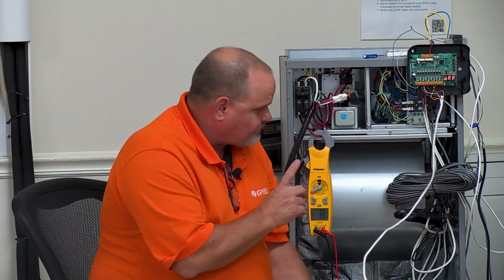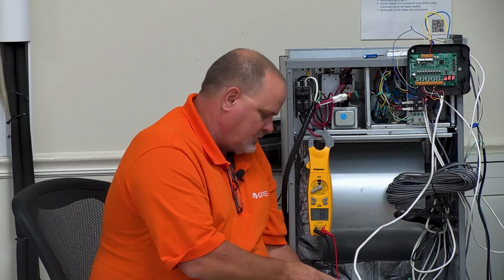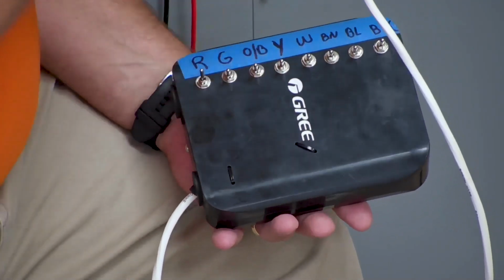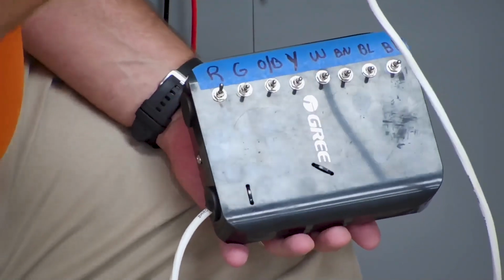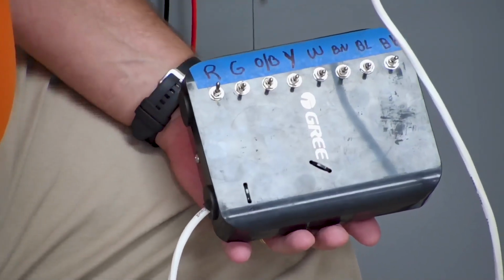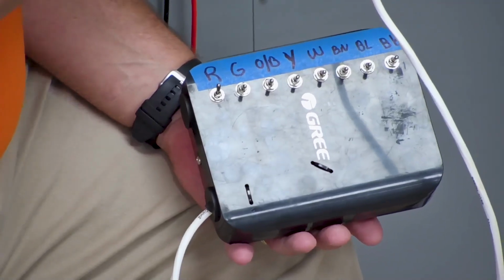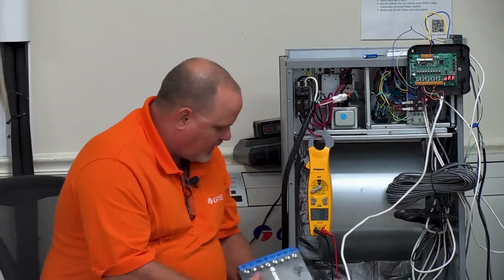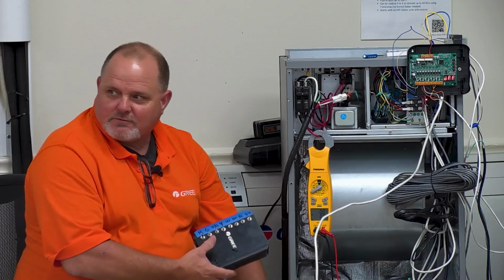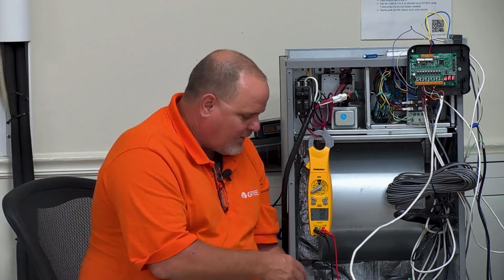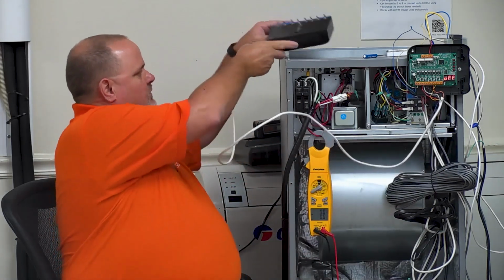So anyway, as I said before, if I give it an electric heat call, which I don't want to do just yet because I want to do a heat pump call first, I can't really simulate electric heat or auxiliary heat operation with this setup. The reason being, as you can probably well see, I don't have any refrigerant pipes going to this, but I do have it hooked to a MultiPro unit. So I don't want to leave it running very long because it's not going to be too happy with me if I do that. But just to show you, I gave it an OB call, so B should be energized. And we'll just verify that right quick.